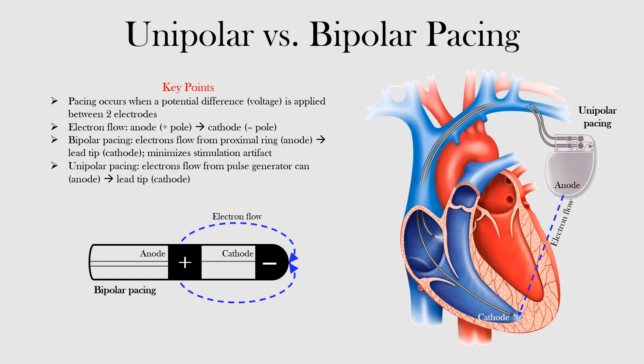Pacing occurs when a potential difference — that is, voltage — is applied between two electrodes. Pacemakers can use either a unipolar or bipolar mode of pacing.